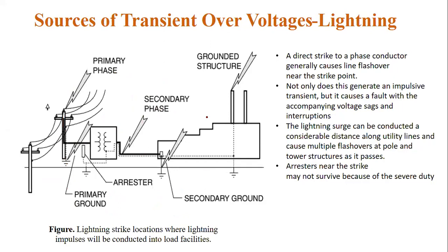if this line is hit on the secondary side of the transformer, this side, you can see this side. So what will happen here? At that time, the secondary ground, nothing but the secondary side of the transformer, will clear the fault. In this case also, before the clearing, some amount of voltage is also injected into the lines or system.